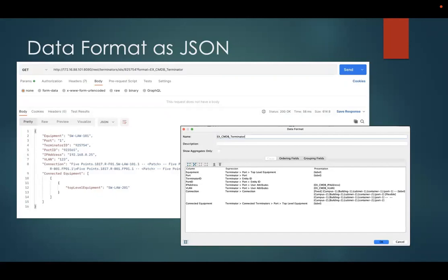It is truly easy, and I could show you in here, but literally you can go in and add a user attribute. You assign it to either a total class of objects or just specific classes. So you can assign it to a patch panel, to every piece of active chassis, or to ports. Those data fields are allowed to be anywhere, and they can be text, integer, real numbers, pull down menus, a whole series of things that you can add to the system. And if you're using pull down menus, those can be updated from the API, pushing additional values into it. So you're not even having to go in and code the additional pick list remotely. You're just pushing it in from your integration.